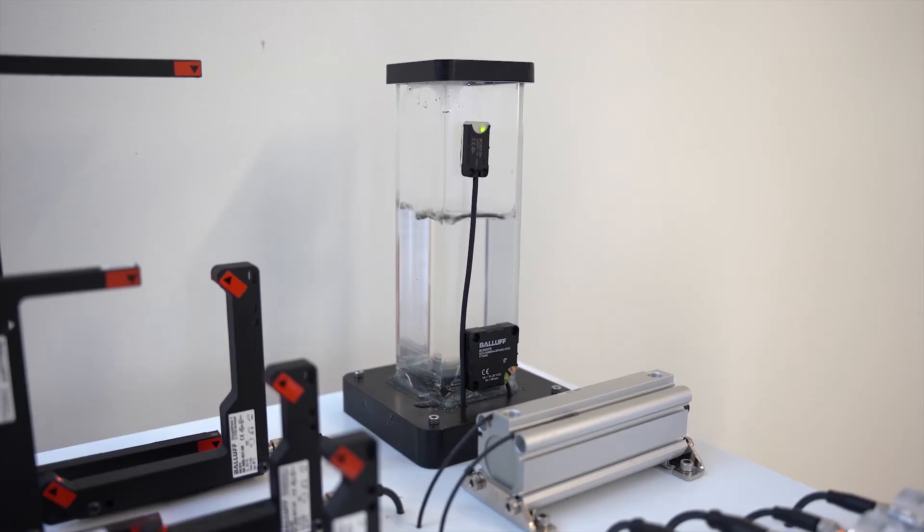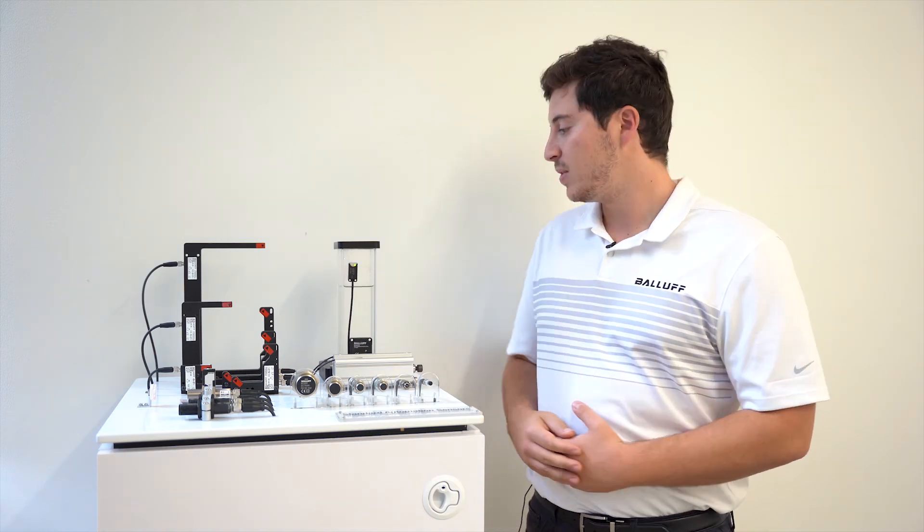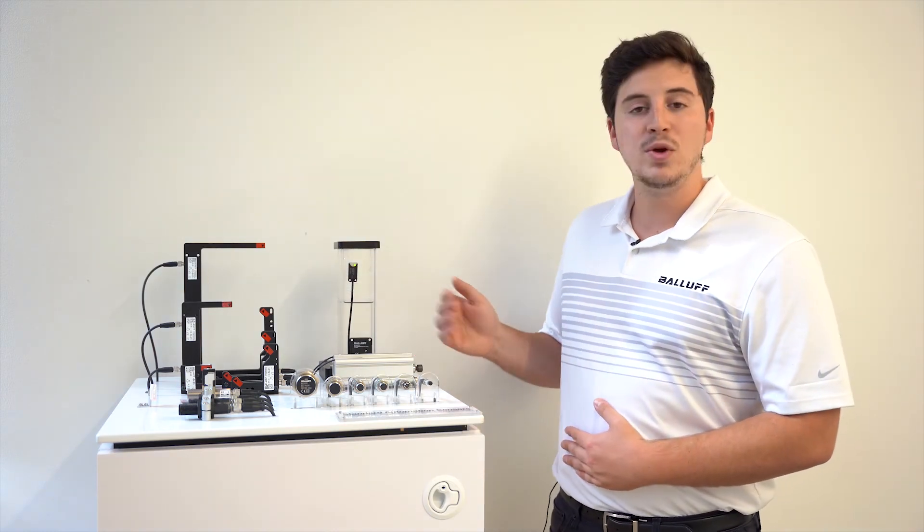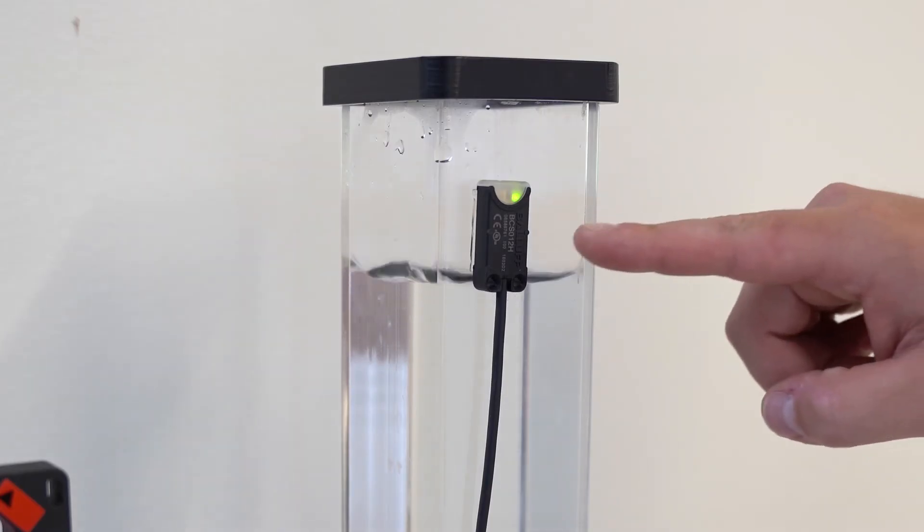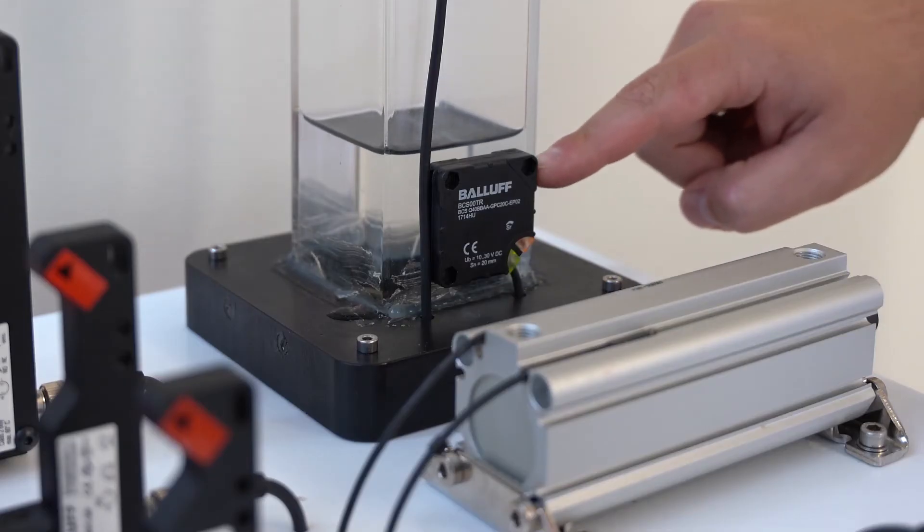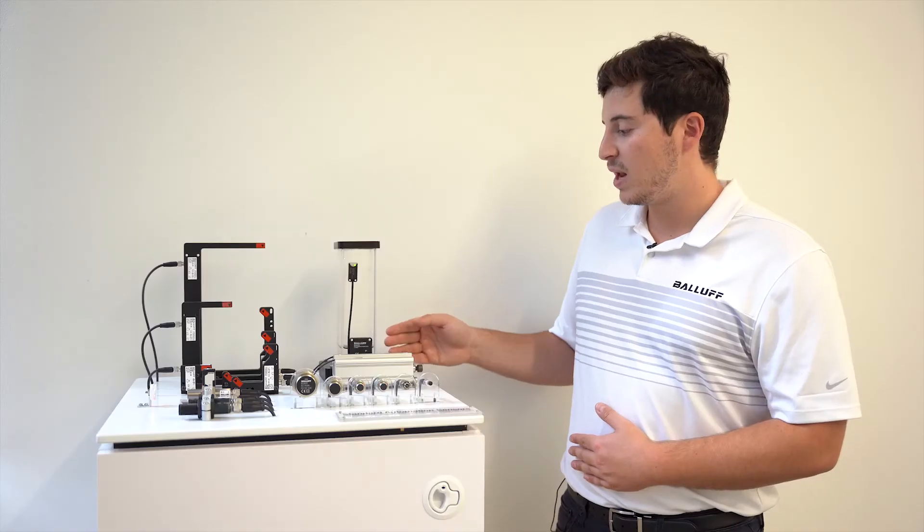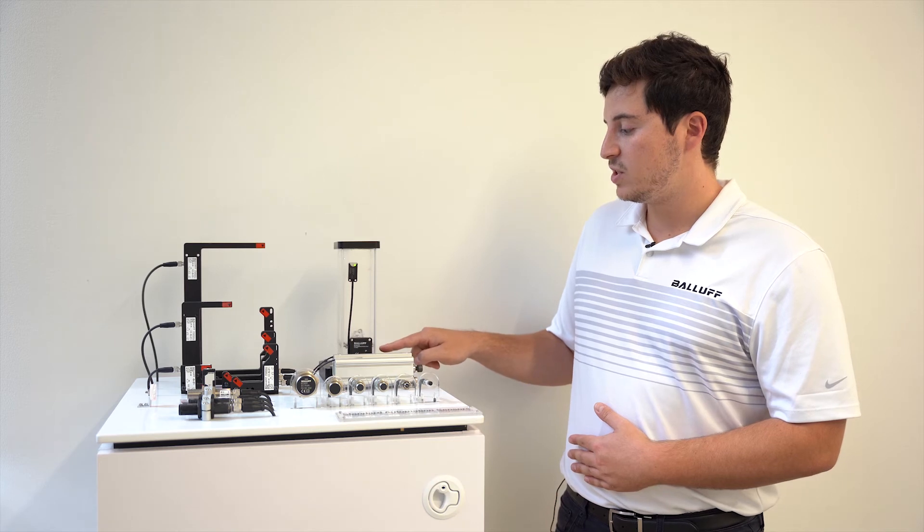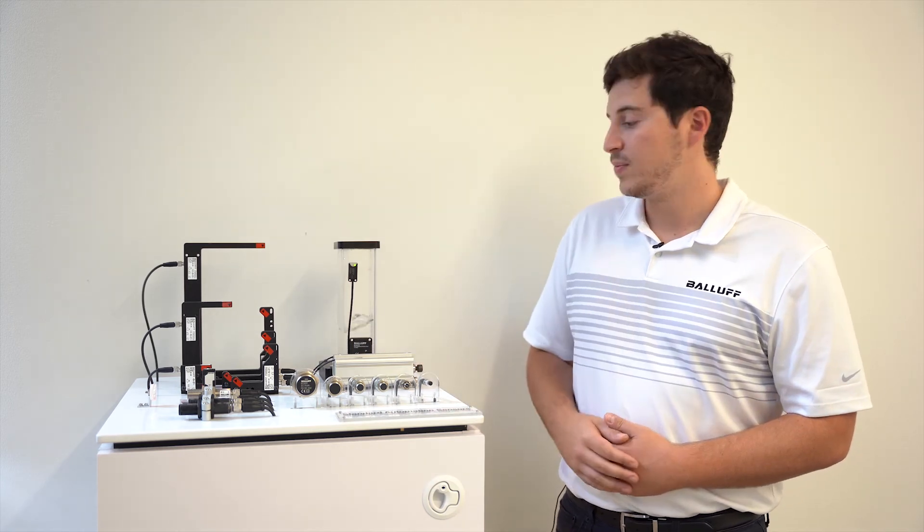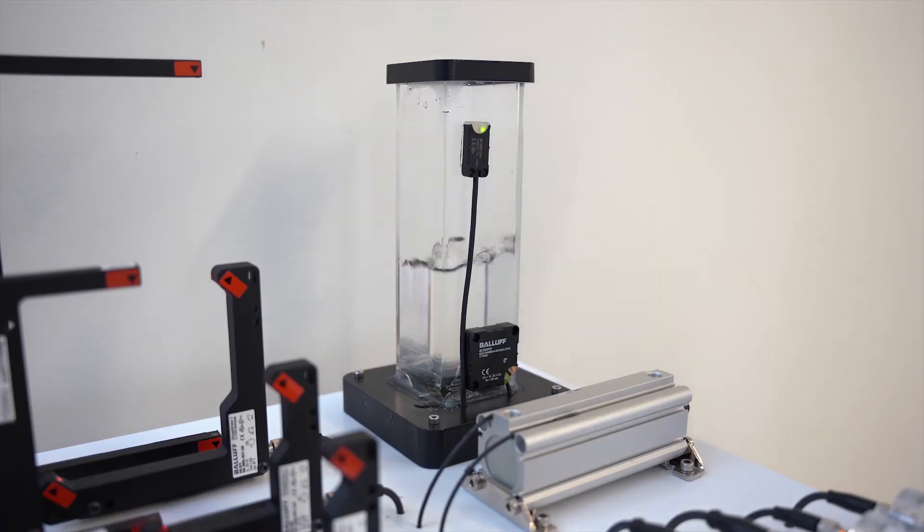Located on the back right here is our level detection demo, and this has two capacitive sensors located on the front, one on the top and one on the bottom. As you can see, as the water reaches the bottom, that sensor can actually see through that plastic tank, detect that water level, and then tell that pump to start filling it up. Same goes for the top. As it reaches the top, it will tell that pump to start draining the water.